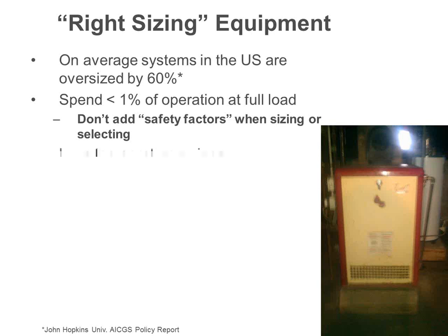Okay. There are different sizing methods. Basically, heat loss calculation is the best method. Manual J is residential, ASHRAE's for other methods in commercial. Load calcs are required by code on a lot of new applications nowadays, and even older ones. You've got to prove that you're there.